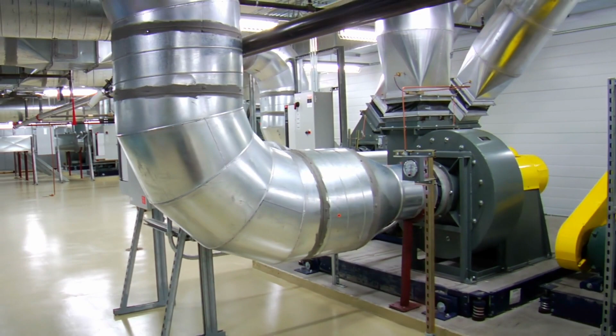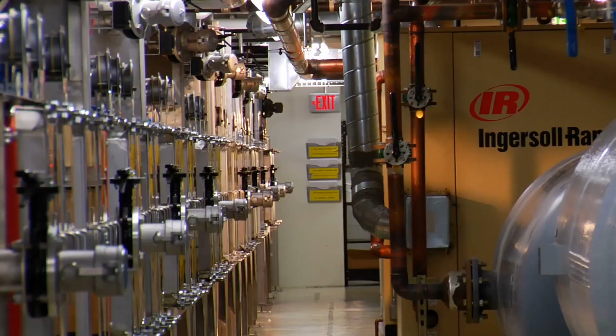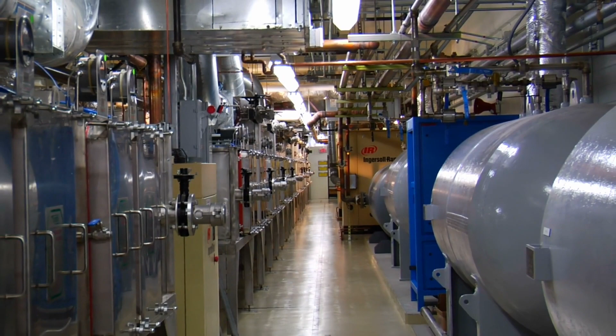Each industry and each project will of course have a process-specific PCN, or process control narrative, that gives the specifics of how the plant process is to function for both normal operating scenarios and fault or contingency conditions. Commissioning is required for all industrial plant processes to verify that the PCN has been correctly implemented in the field, to verify that the project-specific control and operation of the systems is functioning correctly.